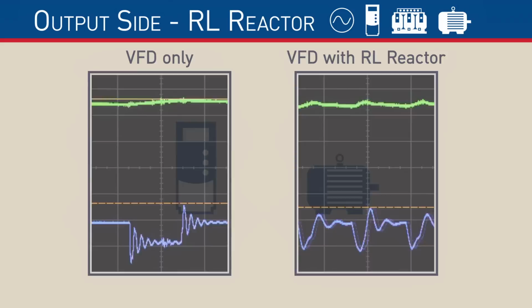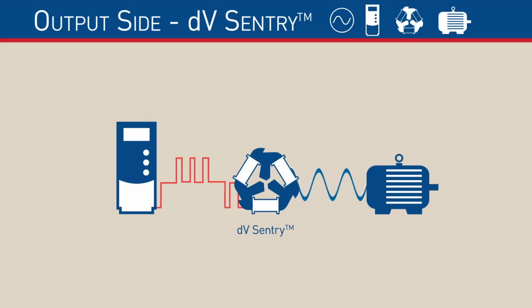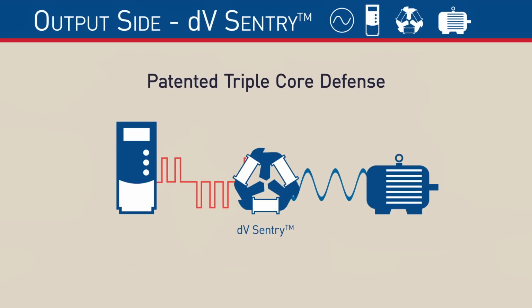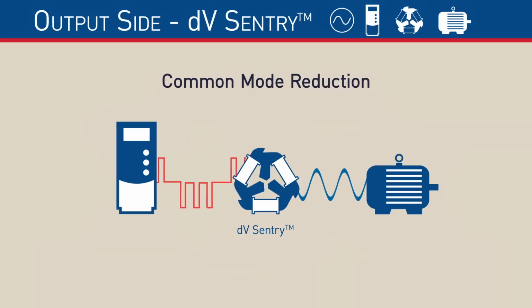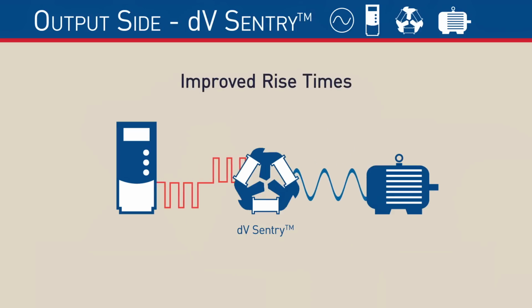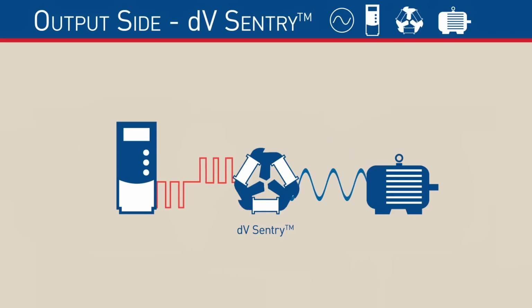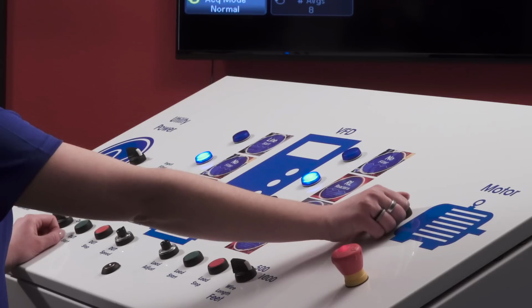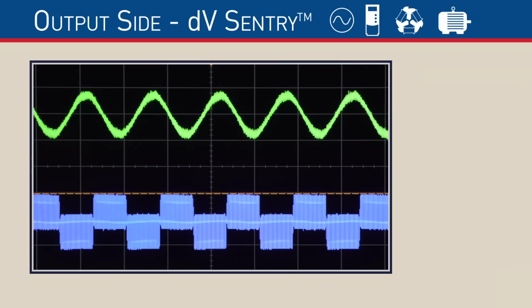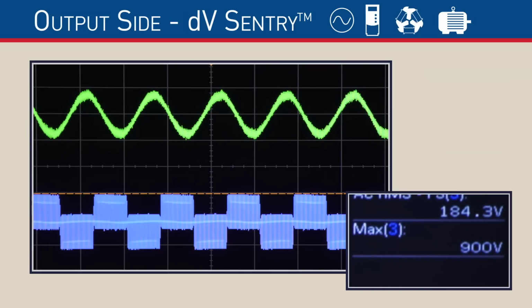We've seen what can be done by adding a simple reactor into the system. But if we want to go a step further, we can add a DV Sentry dV/dt filter. With its patented design, the DV Sentry provides common mode reduction, peak voltage protection, and improved rise times all in one unit out to 1,000 feet of cable. As we switch in the DV Sentry and start the system, we notice our peak voltage has now been reduced from 1400 volts to around 900 volts. This is critical for non-inverter duty motors that are designed with a maximum peak voltage of 1000 volts.